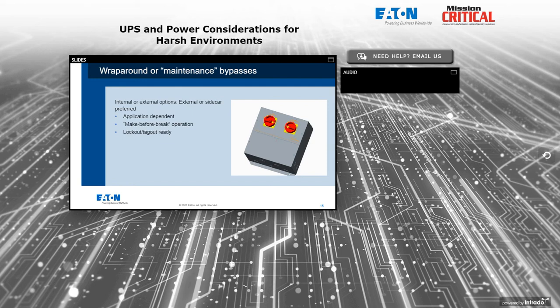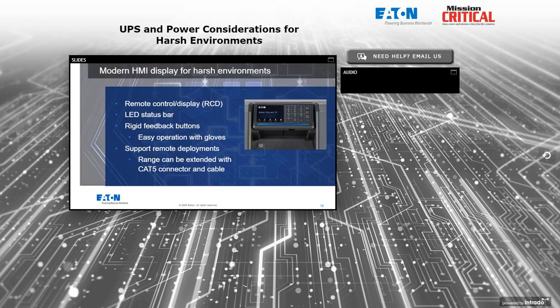The circuit breaker type maintenance bypasses have the slight disadvantage of allowing, unless Kirk key interlocks are used, the case of operator error, where somebody operates a breaker in the wrong sequence and disconnects the critical load, which is not why we buy UPS systems. So rotary switches like the kind you see here are common in industrial environments, and they basically force the proper sequence of operation as you turn the switch from the UPS position, for example, to the bypass position. Just a little more foolproof operation.